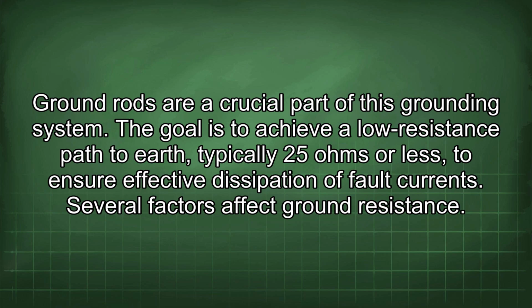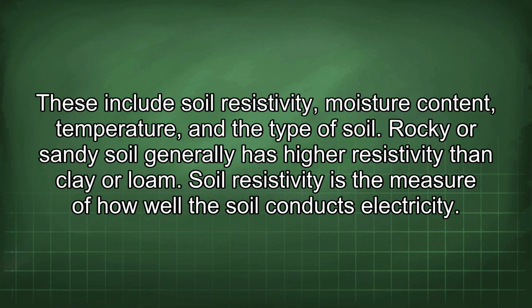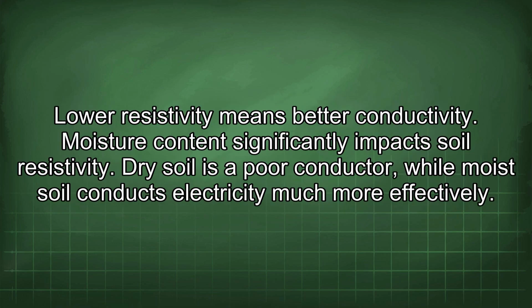The goal is to achieve a low resistance path to earth, typically 25 ohms or less, to ensure effective dissipation of fault currents. Several factors affect ground resistance. These include soil resistivity, moisture content, temperature, and the type of soil. Rocky or sandy soil generally has higher resistivity than clay or loam. Soil resistivity is the measure of how well the soil conducts electricity. Lower resistivity means better conductivity.